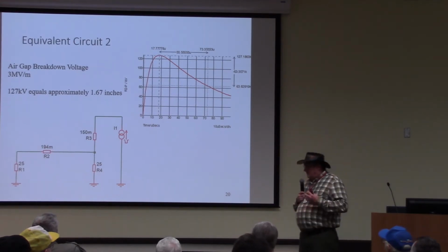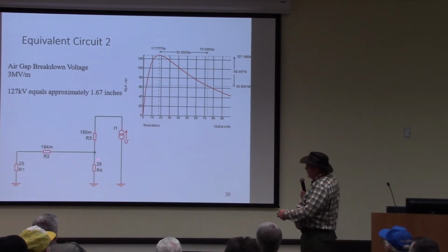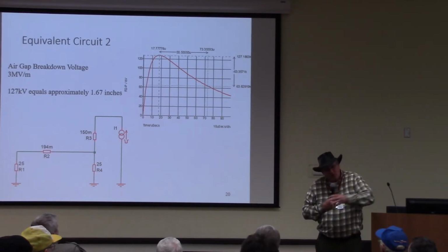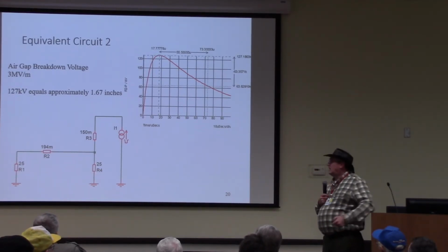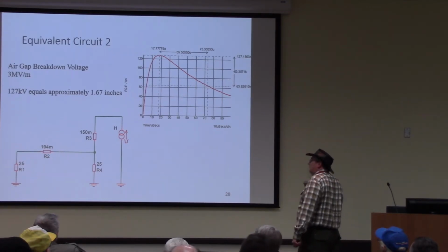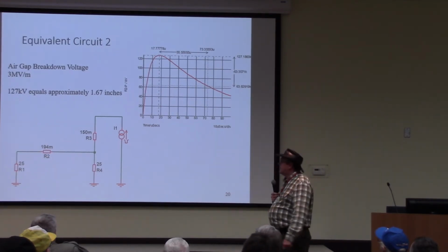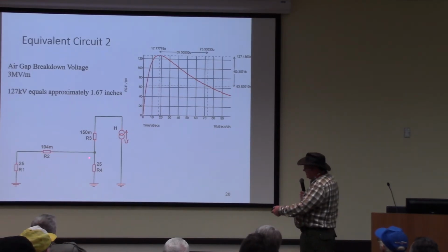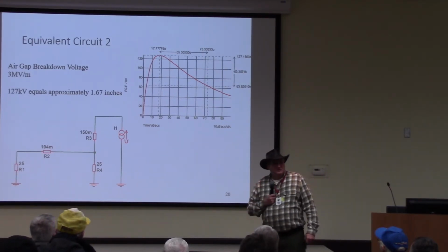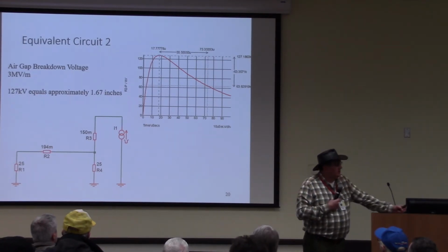What we basically have done is we put a 25 ohm impedance at this point where the cable comes down and enters the house. Now that's better than it was, because now we lowered our threat by half to 127K. But part of the problem is this impedance is high enough, and that's so much current, and this impedance is low enough, that the actual current's going to go through your house still. It's going to go through the green wire safety ground in your house.